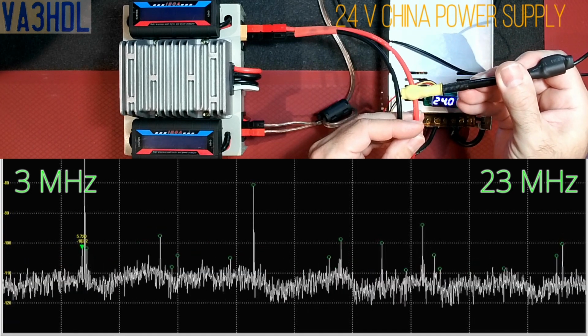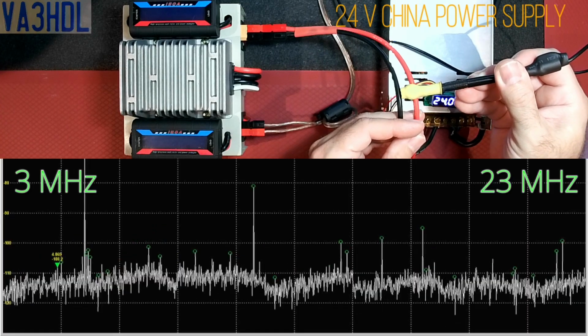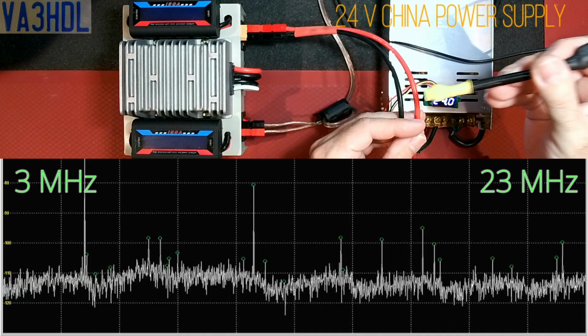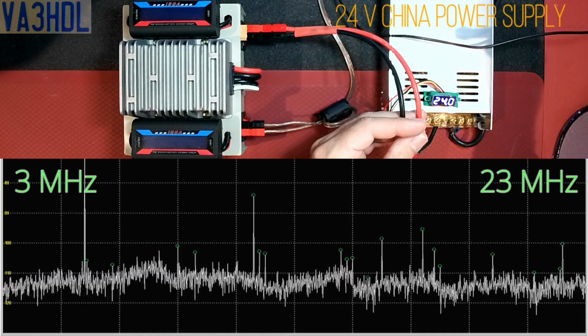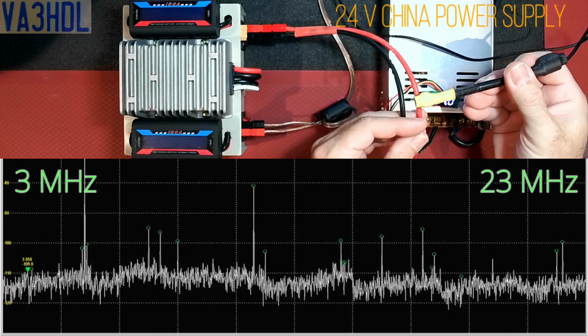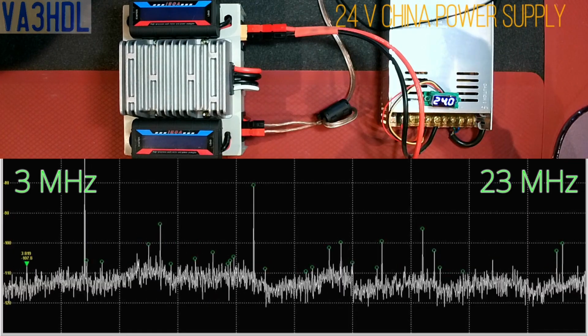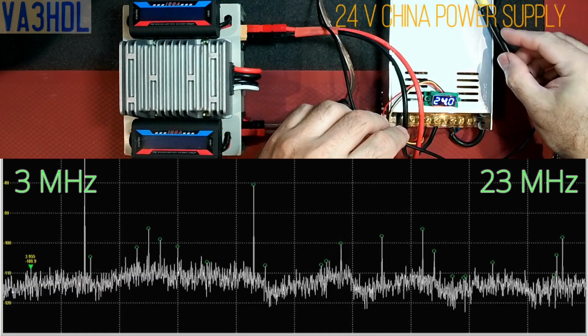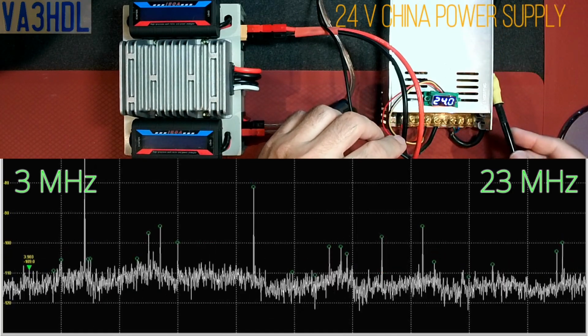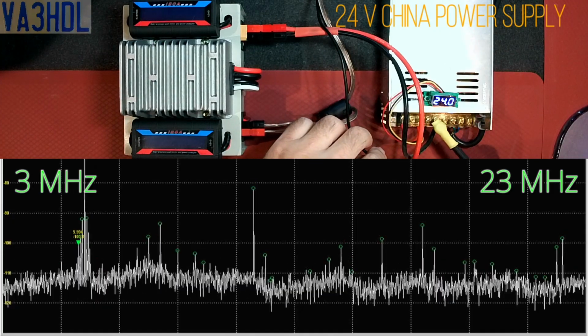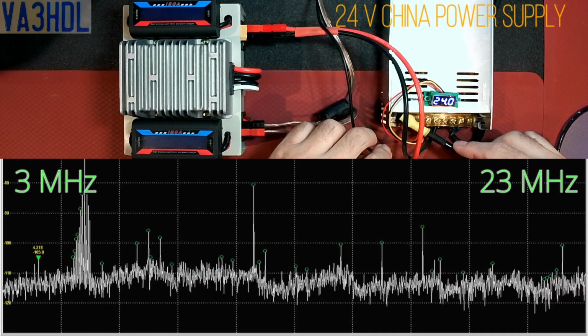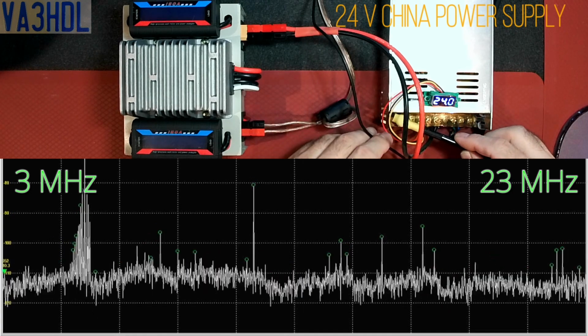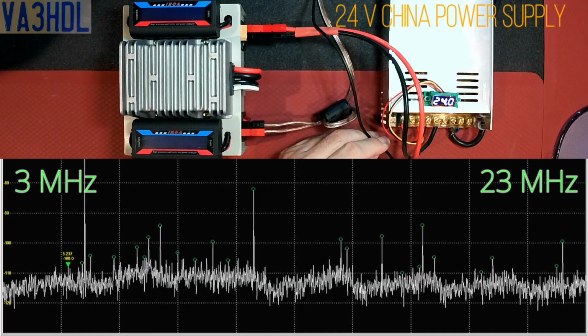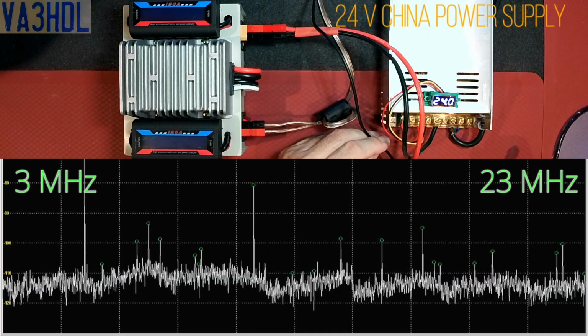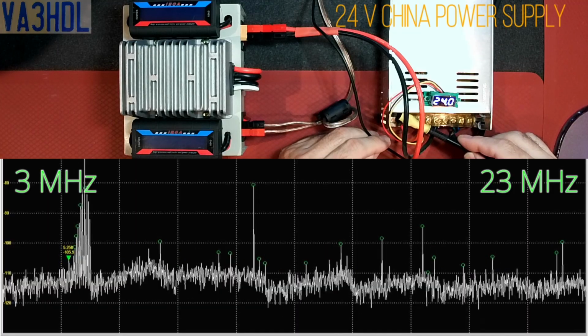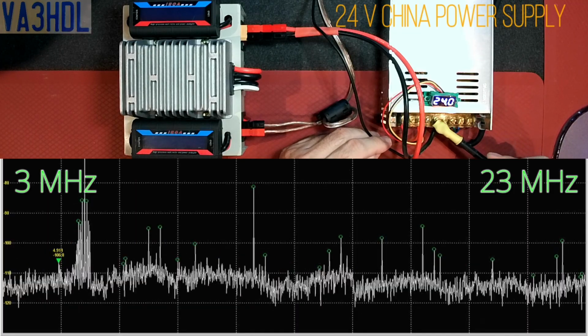There is a little bit of noise here. Let me take the probe out and bring it back in... yeah, there's some, but not a lot. Let's check closer to the power supply itself. On the side it's all aluminum. Near the connector, close to the opening, you can see it. Around 4.5 megahertz, when I come close to the opening, there is noise there, so it's definitely generating noise, and it's leaking out from the openings.